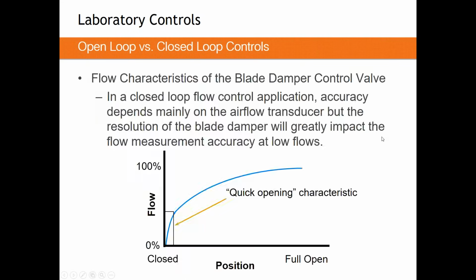Another thing we're going to have to consider is the flow control characteristic of a closed loop valve or of a mechanically pressure dependent valve. All of these devices basically use some sort of damper, whether it's a pivot blade or a butterfly or two dampers or one, doesn't matter. They all suffer from an opening characteristic. Basically, at one point in time, they're closed, and at one more step open, there is now some airflow. So you go from 0 to something.